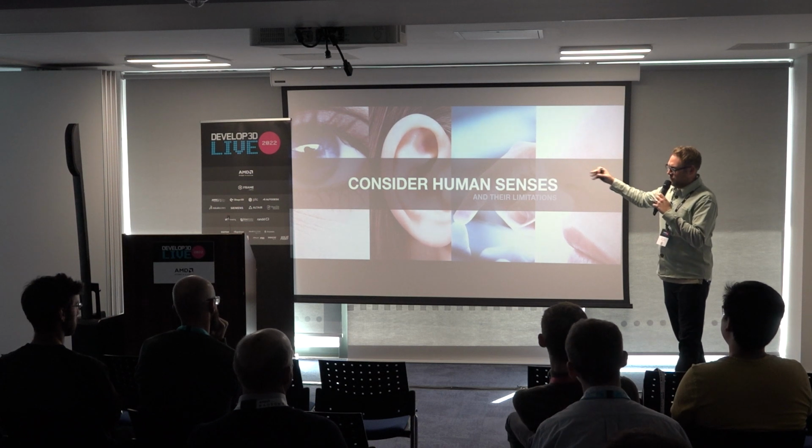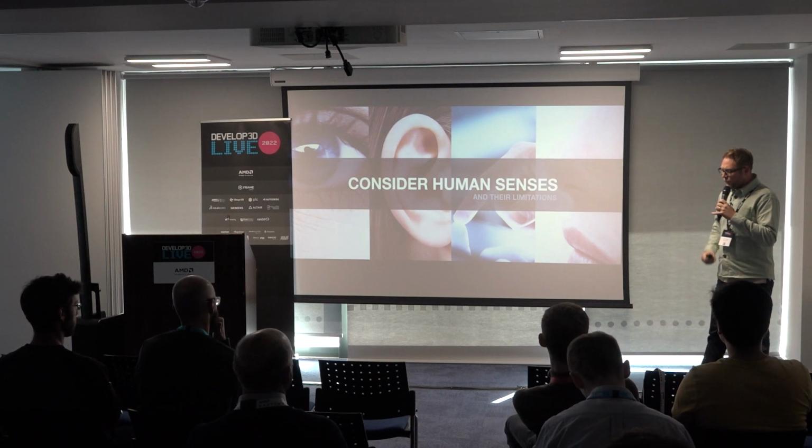Another one is in terms of hearing. We need to realize that interactions, even something like the volume of an alarm on a medical device, should be a conscious decision. It's very easy to just slip into thinking, yeah, well, it's going to have that LED, or it's going to have this alarm. Well, what LED, what color, what size, what shape? If it is an alarm, what volume is that at?